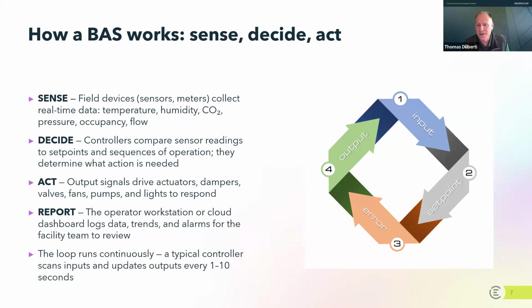And it's that last bullet here. A typical controller scans inputs and updates the system every 1 to 10 seconds. But again, this is a user choice. So somebody at the end of the day is making the decision to make it every 1 second, every 5 seconds, every 10 seconds as these inputs are fed into the system.